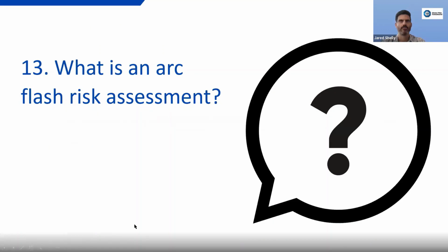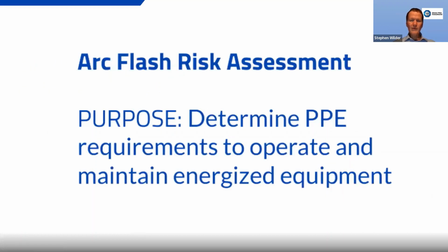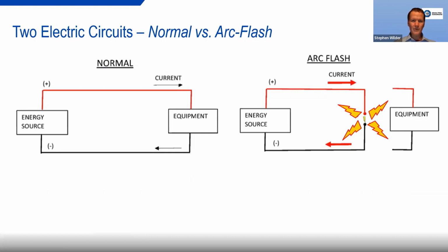You bet. So let's talk finally about arc flash. What is an arc flash risk assessment? Well, with a short circuit, two wires touch. But in an arc flash, if you bring the two wires close enough to each other without touching, there's a little lightning bolt that occurs between them. This is an arc. Again, as I mentioned, it's 35,000 degrees. It's hotter than the surface of the sun, and it can throw a grown man across the room, and the heat and the pressure are just really devastating to lives and property.